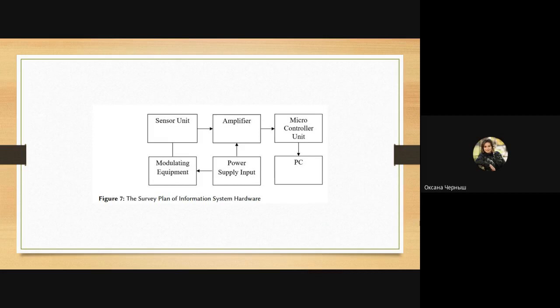Changes in the thickness of the filter are affected by the pulsation of the arterioles. Each pulse wave increases the amount of blood in the arteries and arterioles. The doctor defines this as a pulse rate, and the pulse oximeter considers that as a thickening of the filter. In such a way, the pulse rate and amplitude of the pulse wave are measured.